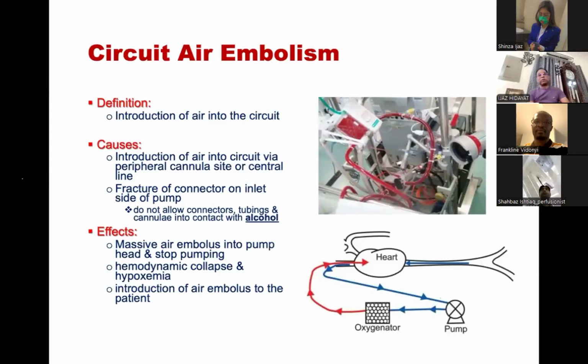So what can be the causes of air in the circuit? Introduction of air into the circuit via a peripheral cannulation site or central line, fracture of the connectors, or the inlet side of the pumps. Now, air can enter especially in VV ECMO. The biggest risk of air is if you are doing VV ECMO and you add an additional cannula, because this is a closed circuit, especially the venous circuit, so there is a chance of sucking more air through that. Air always enters through the access line, not the return line. On the return side you have positive pressure; on the access side you have negative pressure. The source of air is on the negative side, not on the positive side.